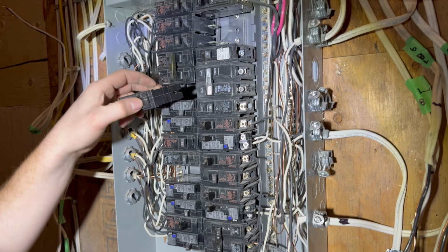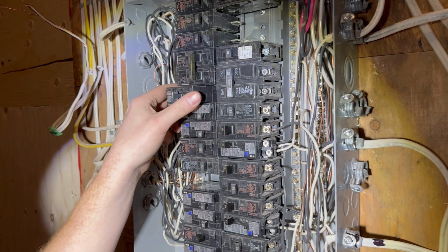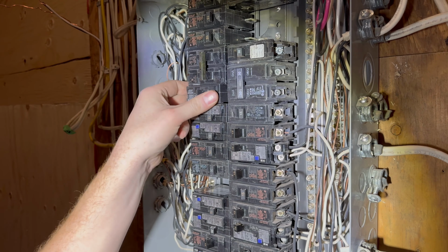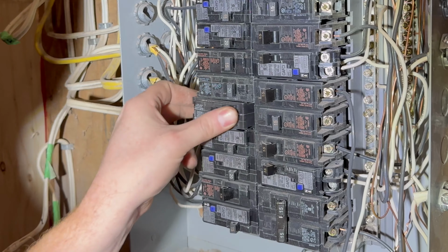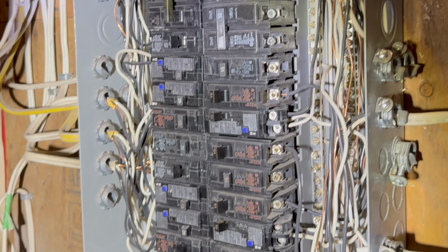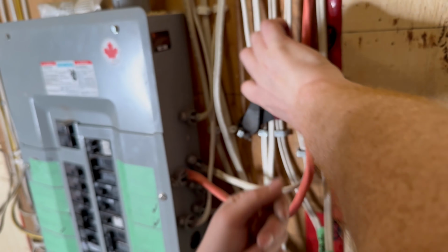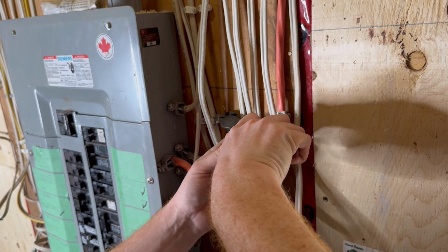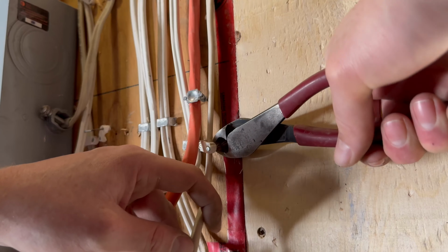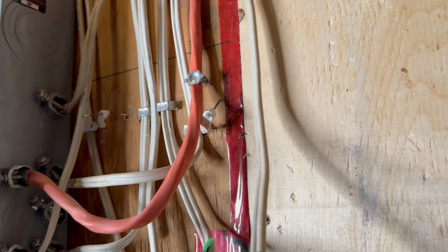With the regular breakers removed from the transfer switch panel, replace them into the main panel so that the holes in the cover are filled when it goes back on. Here Mark is removing the cable staples holding the cables in place, the ones that will be redirected into the manual transfer switch.